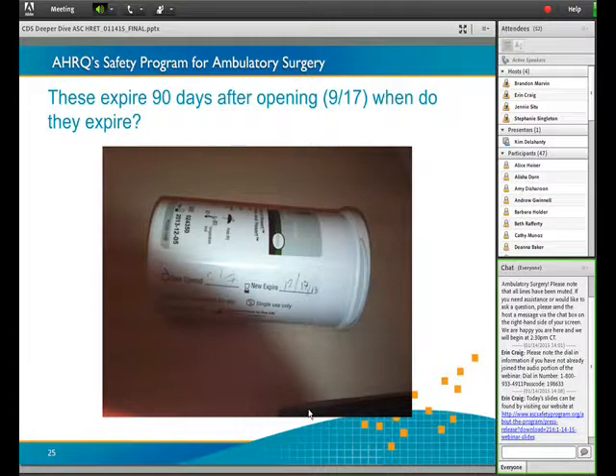Oh, actually, no, this is correct, I apologize. See the manufacture date up there? It says 12/5/2013. That's the real issue here: it says 9/17 to 12/17, which is 90 days, but the manufacturer says this bottle is only good till 12/5, and they let it stay out until 12/17. So not only do you have to look at the 90-day rule, you also have to check the manufacturer date to make sure you don't extend past it.